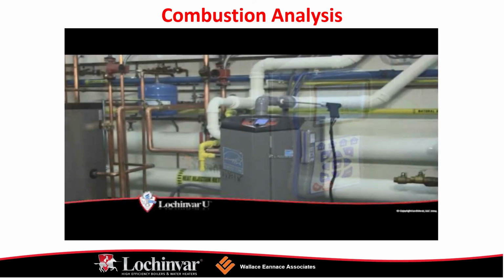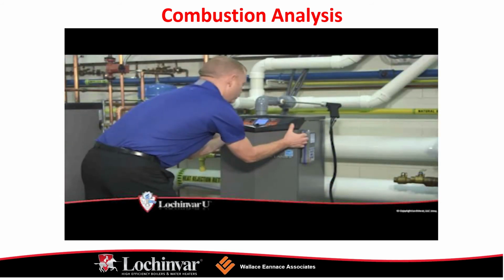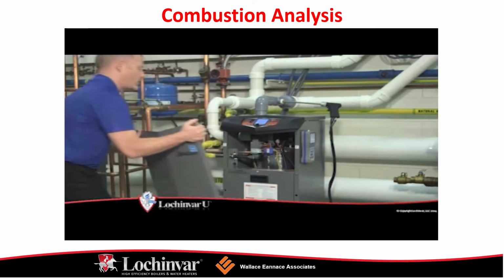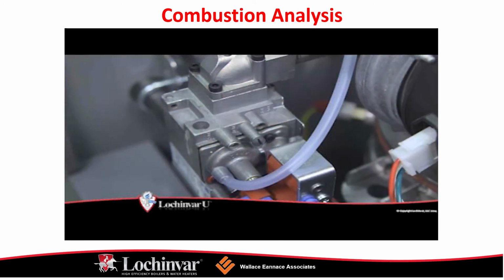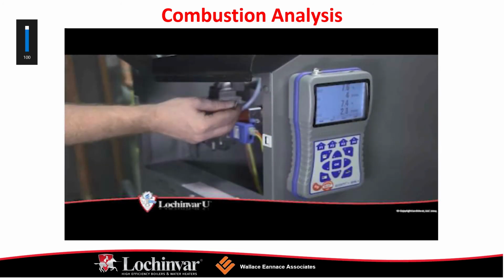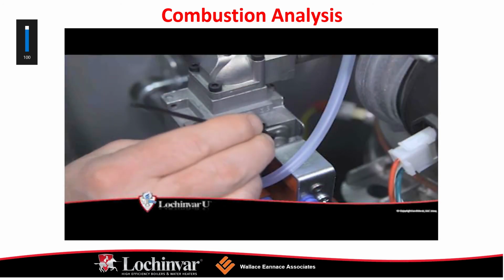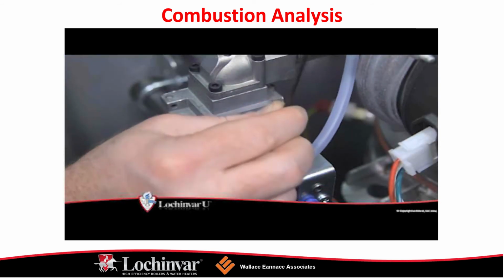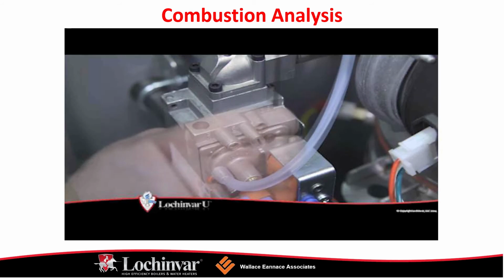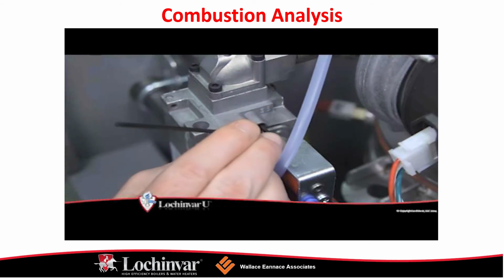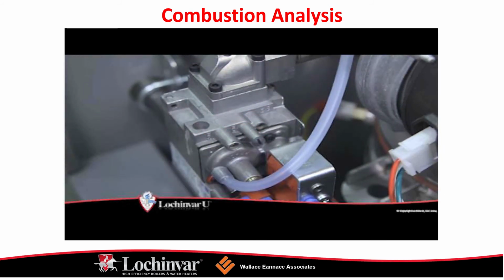Once a unit has modulated its firing rate up to 100%, insert the probe from a combustion analyzer into the hole left by the removal of the plug and measure the combustion. Refer to the flue products table in the service manual for proper combustion levels. If the combustion levels are not within the specified ranges, several items could be the cause.